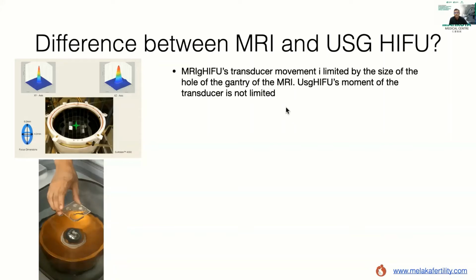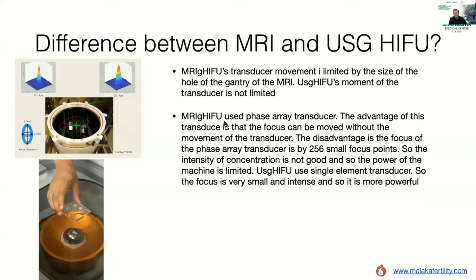Now, in MRI HIFU, the transducer movement is limited by the size of the hole. This is how it is. This is the transducer, and the hole does not move, so the movement of the transducer is very limited. Also, the MRI-based HIFU uses something different, which is called a phase array transducer. The advantage of this transducer is that the focus can be moved without movement of the transducer. But the disadvantage is that the focus of the phase array transducer is made by 256 small focal points. So the intensity and concentration is not so good, and the power of the machine is limited.